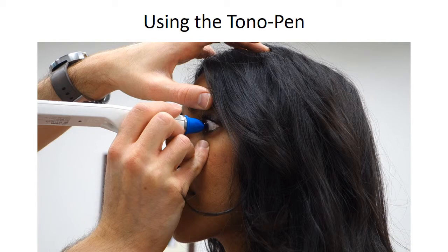It's very important not to apply pressure to the eyeball with your fingers as you're holding the eyelids apart, since this can increase the intraocular pressure reading. You will want to hold the eyelids as we discussed before. Touch by the lash margin and touch it up to the bony part of the periorbital area. You do not want to press on the eyeball itself. Again, a chirp will sound every time a valid reading is obtained. After several readings, a final beep will sound, and the averaged IOP measurement will appear on the display.